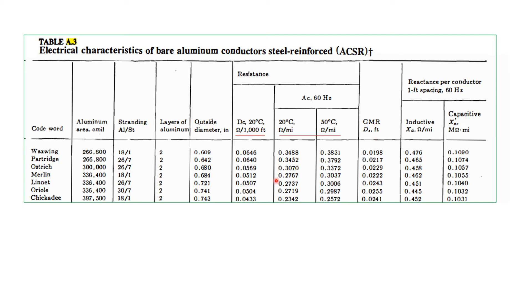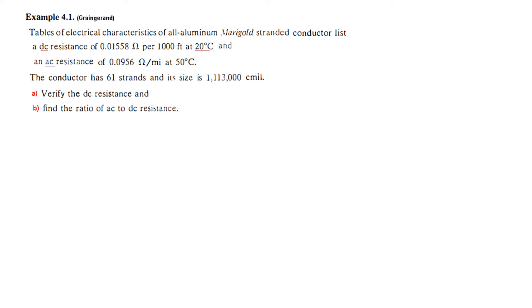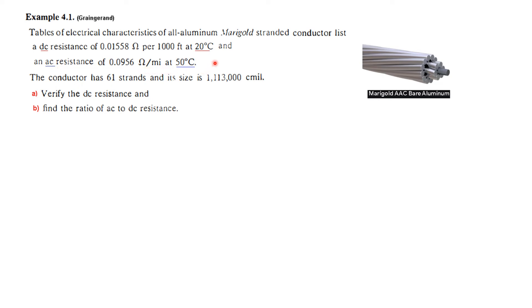For Example 4.1, the table of electrical characteristics of the Marigold AAC aluminum conductor is used. The Marigold conductor has 61 strands and its size is 1,113,000 cmil. We need to verify the DC resistance value from the table, and then calculate the ratio of AC resistance to DC resistance.